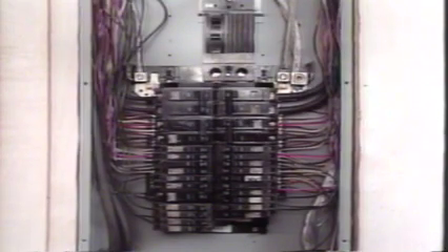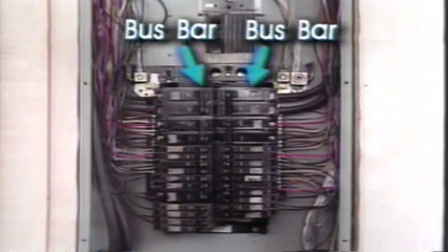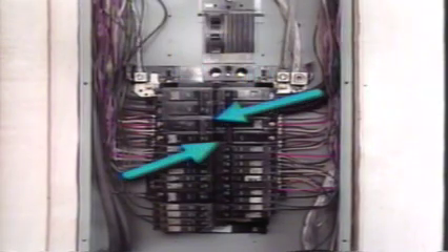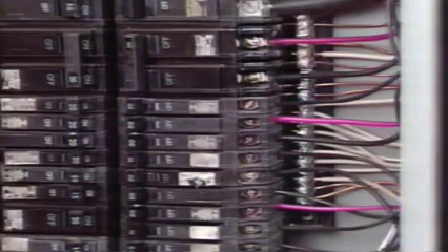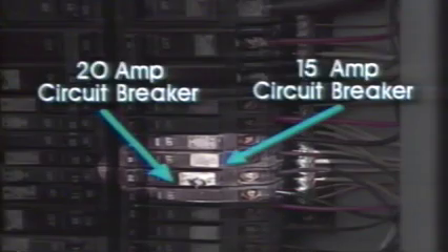Each side of the main circuit breaker is connected to a bus bar. These two hot bus bars each receive 120 volts of power for distribution to the independent branch circuits. The two bus bars are separated by plastic insulators to keep the 120 volt lines independent of each other. This circuit breaker is called a single pole 120 volt breaker, meaning it has only one hot line or voltage source, and it attaches to and draws current from only one bus bar.